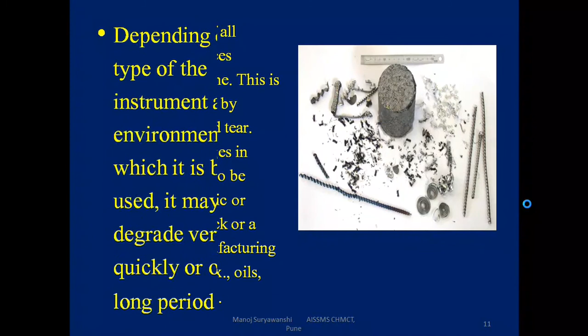Depending on the type of instrument and the environment in which it is being used, it may degrade very quickly or over a long period of time. Like I have mentioned, if you are taking care of each and every piece of equipment properly, and after every interval you are doing proper oiling, proper maintenance, proper servicing, you won't face any kind of calibration fault or calibration issues. But if the equipment is not handled properly, and it is not being cleaned properly, and it's kind of rough use in a particular area, so obviously you need a calibration process.